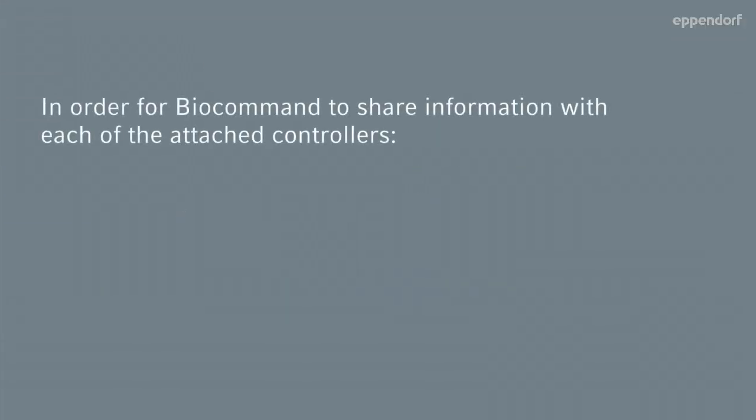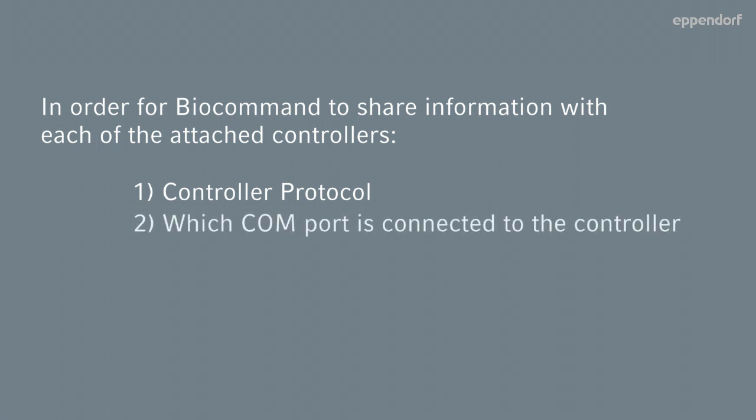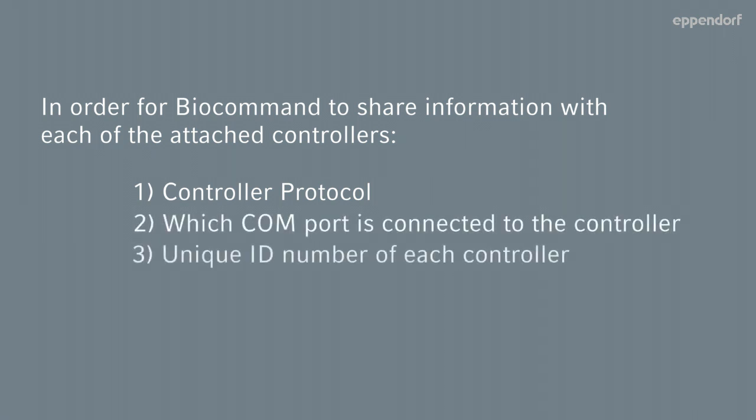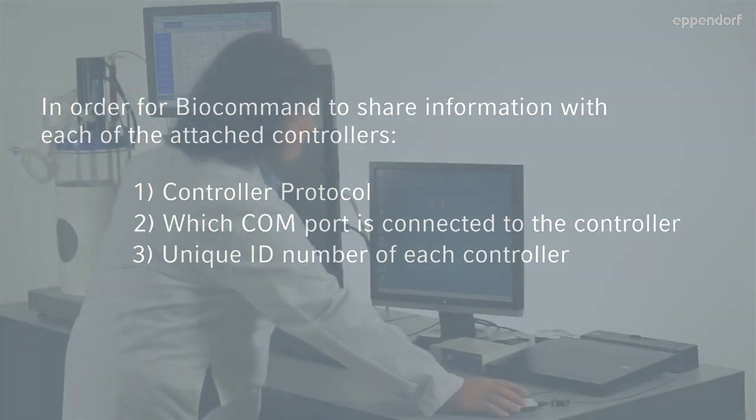In order for BioCommand to share information with each of the attached controllers, three essential pieces of information must be provided to the software: the controller protocol, which communication port is connected to the controller, and the unique ID number of each controller.